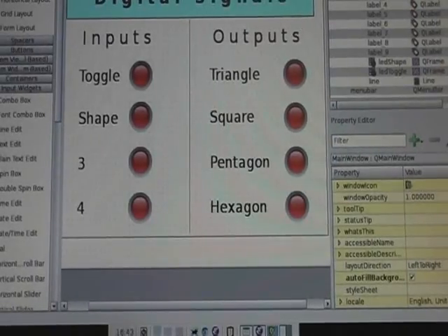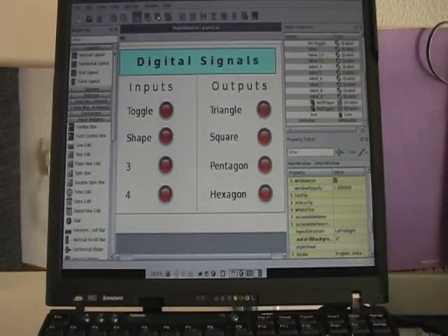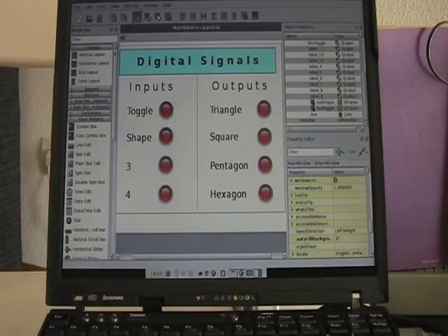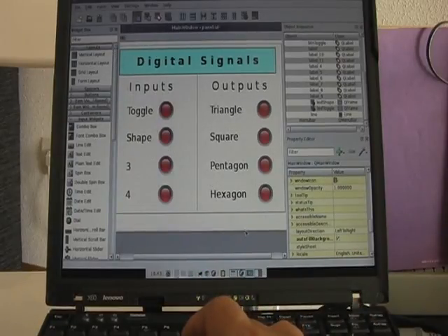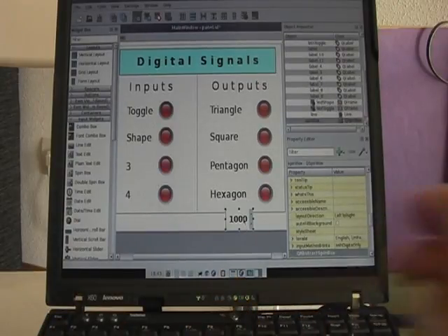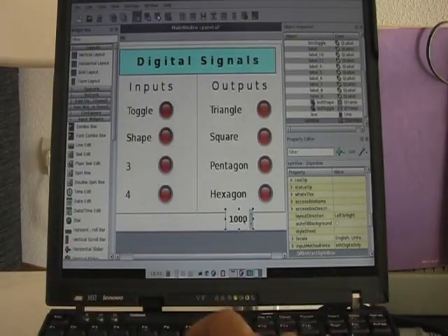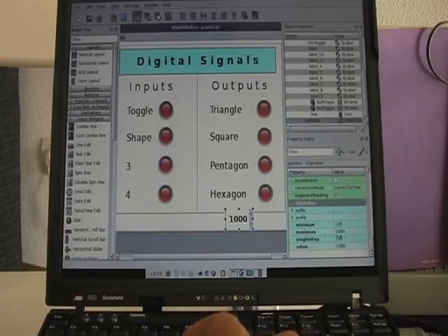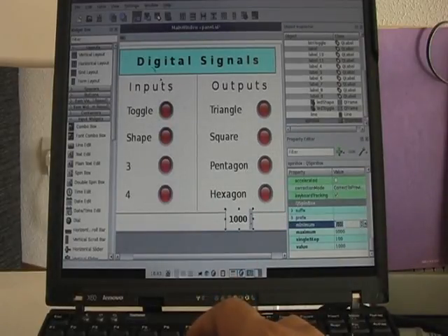So we go to the engineering station, this one here, and we see here the graphics designer, and now in the graphics designer I will add the spin box that I have created before. This spin box has now a default value of 1 second, 1,000 milliseconds, and a minimum of 100. Saying this is okay, I save it, and the name of this object is spinbox2.